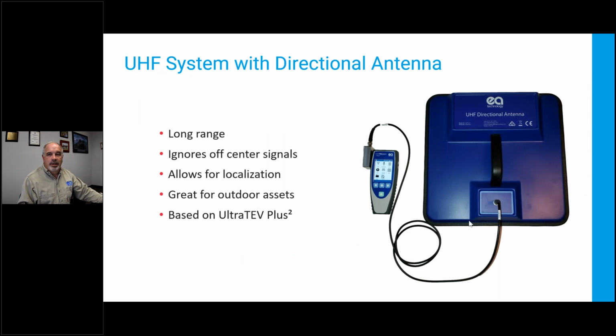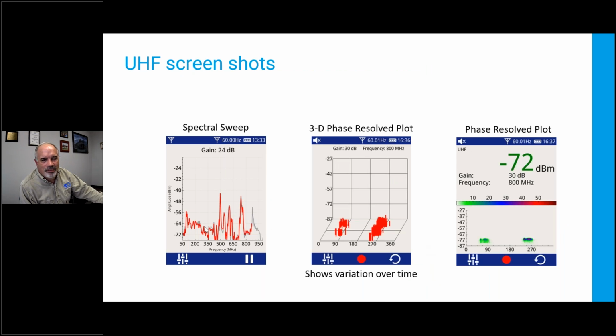All right, so here's our UHF system. It's an antenna and an adapter for the box, and it's a very directional antenna. It's got about a 45-degree cone, so you can walk up to individual insulators, A, B, C. I used this in Chile, and I was able to tell them which one of their insulators needed cleaning just by picking up the UHF emissions from the insulators. There's a variety of different screens available. We've got a spectral plot if you like the EMI type thing, the 3D phase resolved plot, which I find the most useful, and the conventional phase resolved plot.